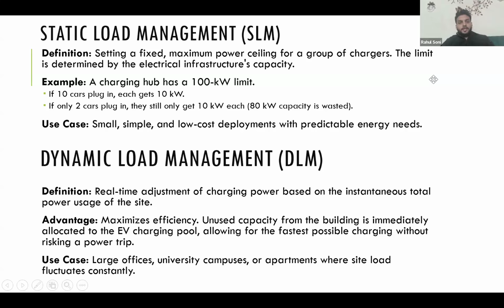In case of static load management, we fix a maximum power for a group of chargers. The maximum charger limit is the infrastructure capacity, which means if 10 cars plug in, each gets 10 kilowatts. If you have a 100 kilowatt limit, you can have 10 cars charging at 10 kilowatts each at that point. If only two cars are plugged in, you still only need a maximum of 10 kilowatts each, so 80 kilowatts is wasted.